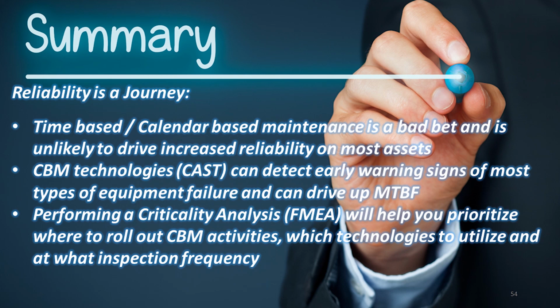Condition-based technologies can detect those problems. You have to understand the mode of failure, the effect of the failure, what technology to use, and the interval of failure, which drives your interval of inspection. We can use all those different technologies to try to detect and correct those problems. Most of these have to be done energized, and because of NFPA 70E's changes, we've got to be really careful about how we do those things energized.